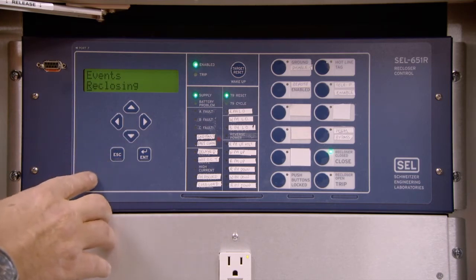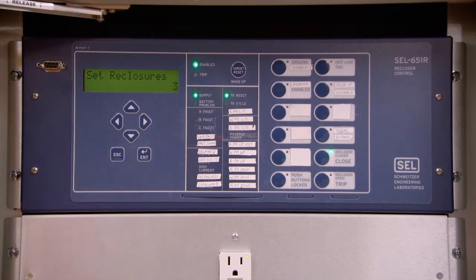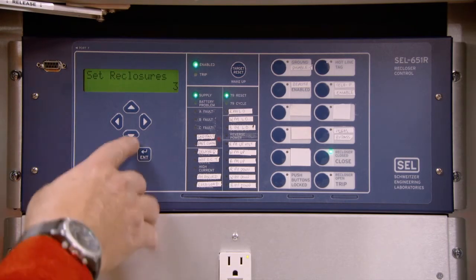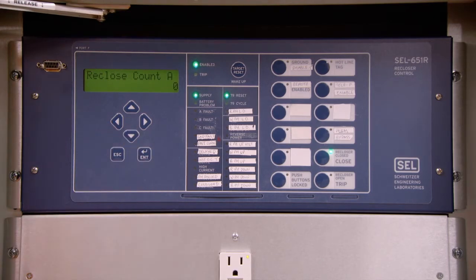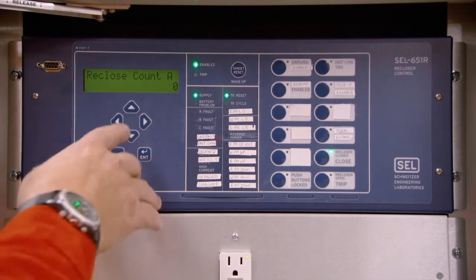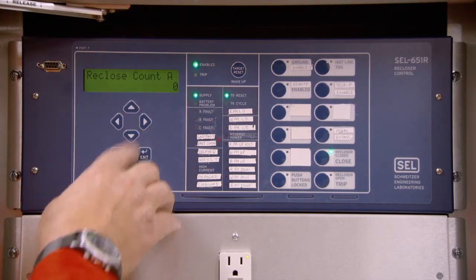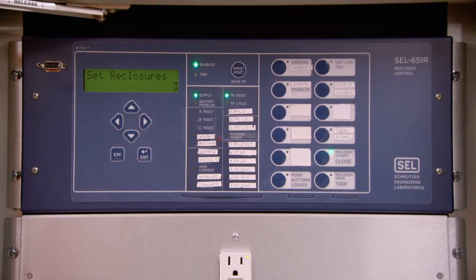We press Enter, and we can see the unit is set for 3 recloser attempts. When the unit is set for 3 recloser attempts, you have 4 shots until lockout. The first operation will be counted as 1. The second operation will be counted as 2. The third operation will be counted as 3. It will not reclose after the fourth operation.